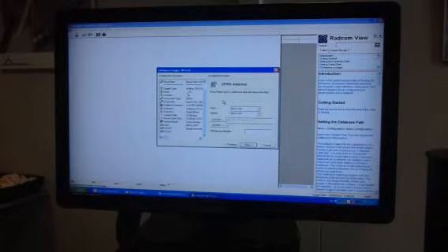and then it gives you the option of the GPRS address. All our loggers now are sending in the data via UDP, and the alarms are set up as UDP as well. In the first box you should have the address of the data gate where the data is going to be sent to.